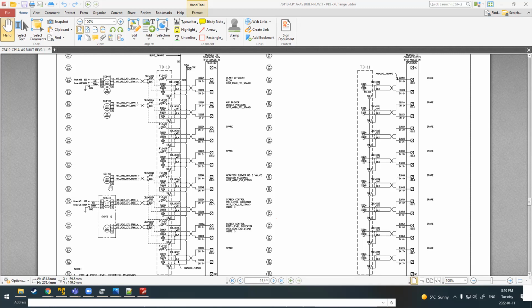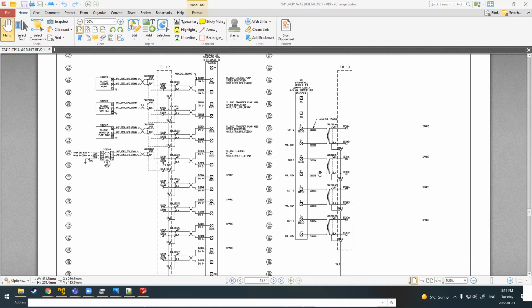Where you see this, it looks like a valve positioner. Valve position feedback actually receives 24 volts from the panel. It goes out to the device and then loops back in, and there's a jumper to return that to 0 VDC. That's called a loop power device. If that shows up anywhere on a quiz, it'll be bonus marks, because that's just something that'll burn you in the future. Just wait for it.